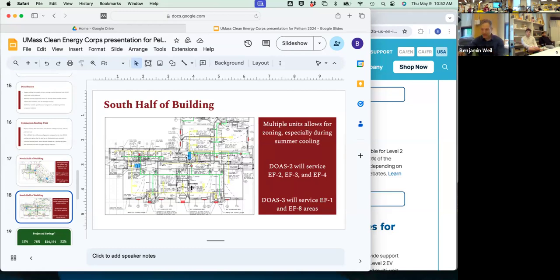So the point that Oliver was making about this unit in particular, which is basically in the location of the current air conditioning unit for the office, is that it can have zone dampers. Because all of these are variable speed pieces of equipment, if you take these zones off, whether you're in heating or cooling, those dampers close because somebody said they're not operating. The machine slows itself way down, and you're basically resizing dynamically for the system. It's like a variable volume system, but zone-wise.